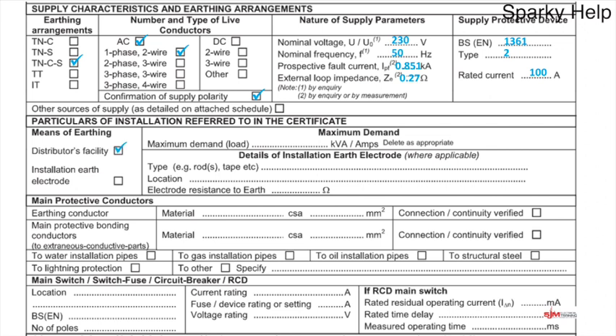Moving on down, particulars of installation, we've got earthing means, and we've got the distributor's facility because it's a TN-C-S. If it was a TT, we would be putting an earth electrode. We may well be putting earth electrodes in more and more. We don't know. We'll wait and see.